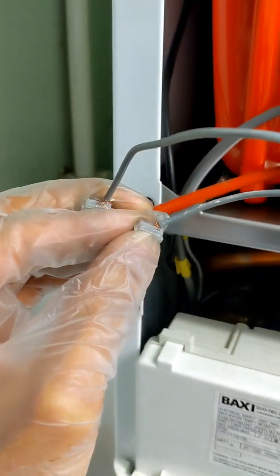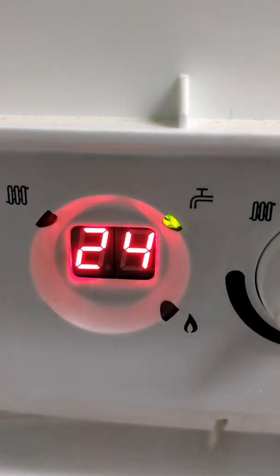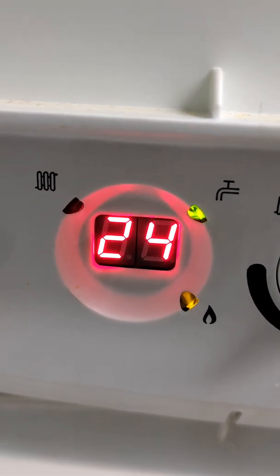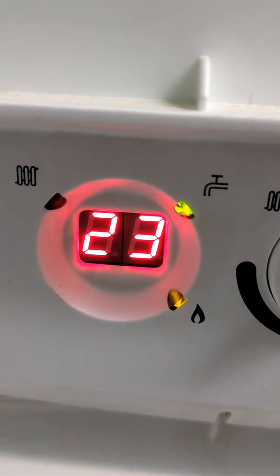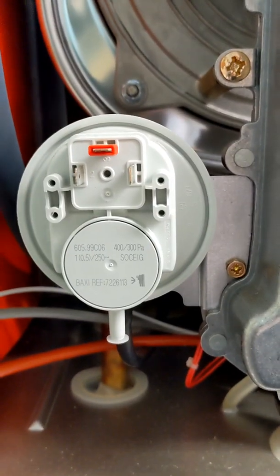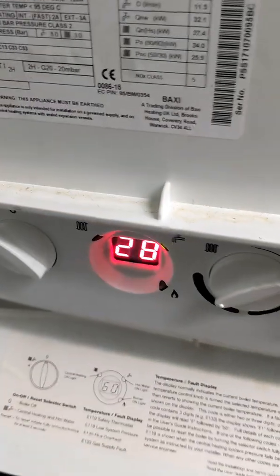As soon as I've bridged that up, the boiler has gone straight into command mode. It's recognized that continuity there. But as soon as I break that, we get E28 again.